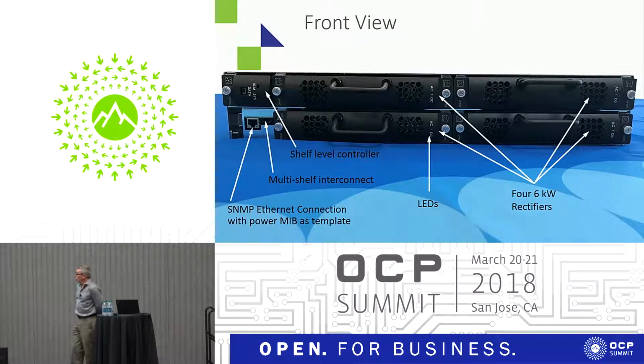There are actually two ports there. One is for Ethernet communications, and the second is what we call a multi-shelf interconnect. This is so that should you have need for more than 24 kilowatts in a rack, you can put in a second rack, and the 2 racks will talk to each other and share power correctly between all of the rectifiers in 2 racks. In theory, you can add more, but we don't anticipate people wanting more than 2 racks at this point.